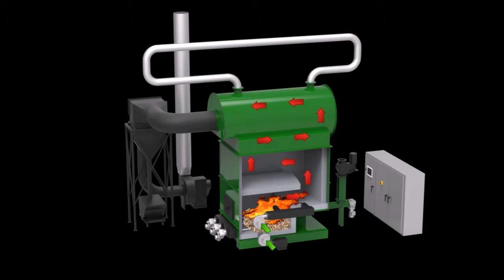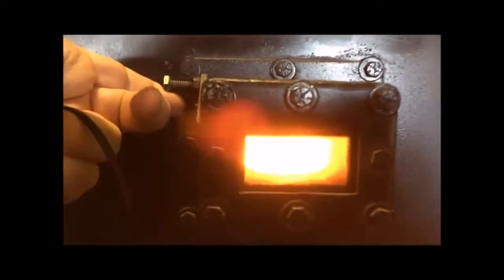Air is blown into the sides of the combustion chamber to feed the combustion flames and increase the combustion temperature up to 1,800 degrees Fahrenheit. In these shots of different systems, we can see how the combustion chamber looks different in each case. Using the controls, the fuel feed and the air can be adjusted to reduce the temperature and adapt to specific requirements, such as emissions requirements. Sulfur and nitrogen dioxide emissions can be very low with this method. The wood chip fuel has 10 million BTUs per ton, making it very suitable for this task.